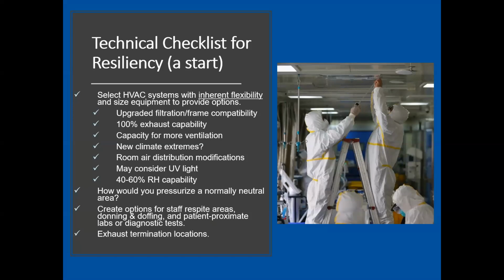So having a good space for that is really important. Thinking about where the exhaust goes out of a building - if you run in 100% outside air economizer mode, you're essentially exhausting that space. But normally we just think of that air going out of a building as relief air, and it doesn't get treated with the same care as far as where that termination location is, as it would if it were known exhaust. But if you're putting infected people in an area and exhausting that by running an HVAC system in economizer mode, you've really got to make sure that relief air doesn't get re-entrained back into the building.